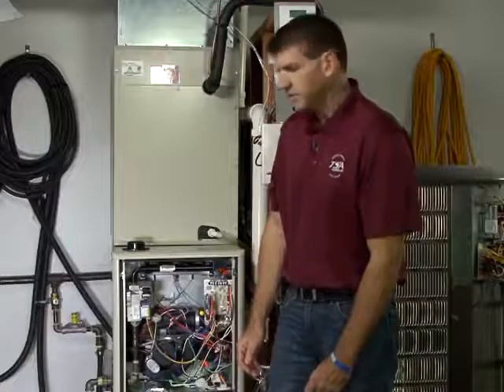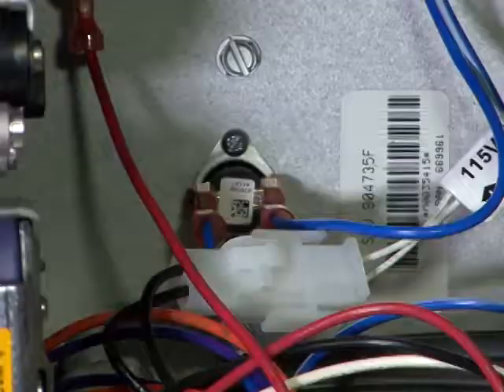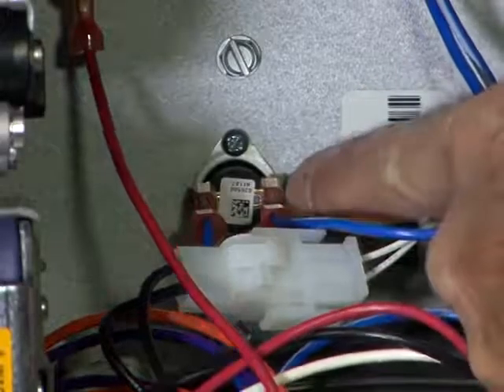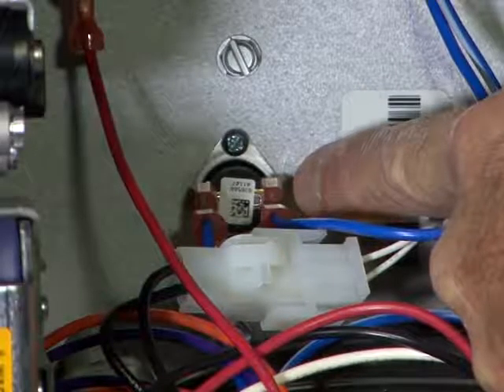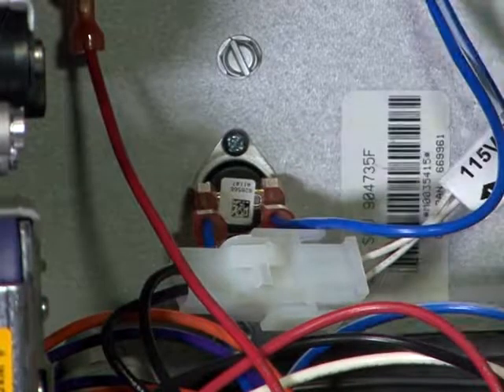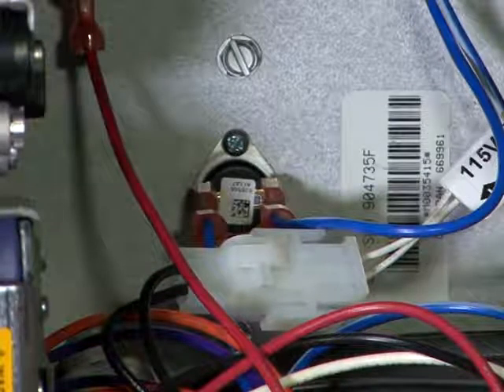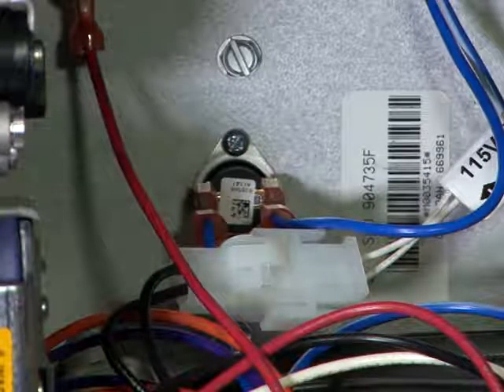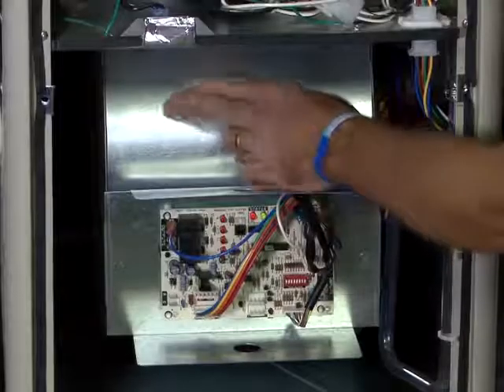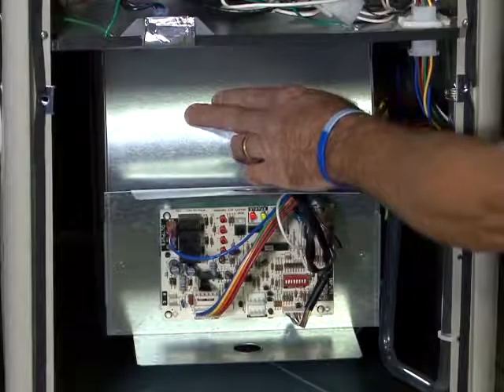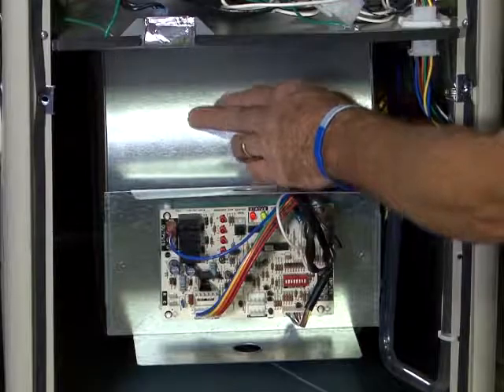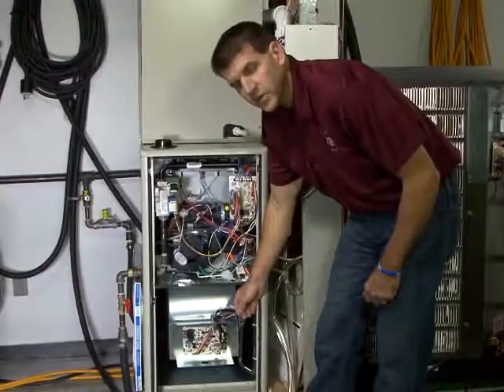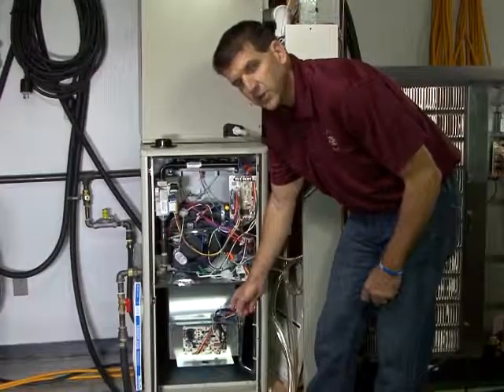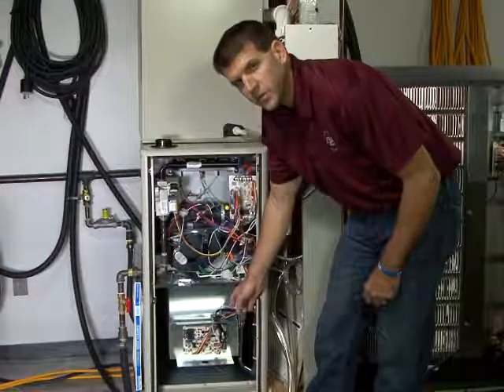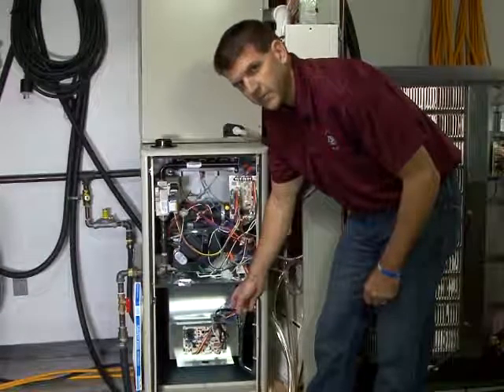Our limit switches, we're going to have a main air temperature limit, which is a surface mount switch that monitors the temperature within the heat exchanger itself. This is an automatic reset type switch. Down in the blower compartment, we have two limit switches that are mounted to the blower housing. These two switches monitor the temperature in the blower housing area. These switches are also automatic reset type.